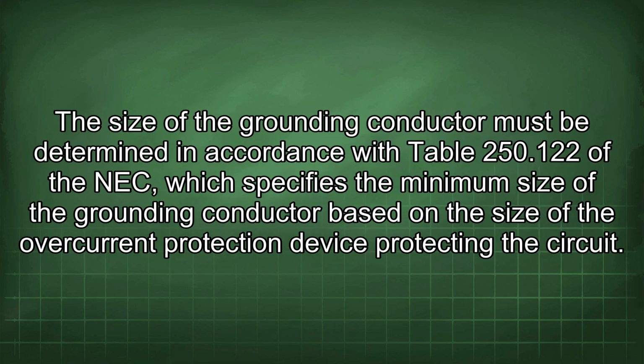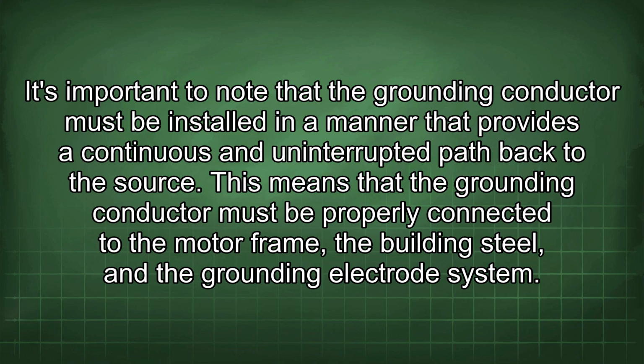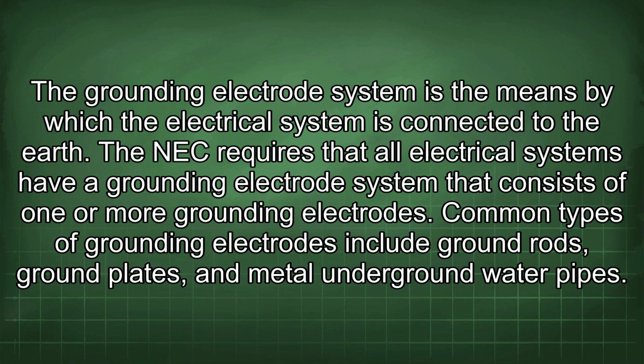The size of the grounding conductor must be determined in accordance with Table 250.122 of the NEC, which specifies the minimum size of the grounding conductor based on the size of the overcurrent protection device protecting the circuit. It's important to note that the grounding conductor must be installed in a manner that provides a continuous and uninterrupted path back to the source. This means that the grounding conductor must be properly connected to the motor frame, the building steel, and the grounding electrode system. The grounding electrode system is the means by which the electrical system is connected to the earth.